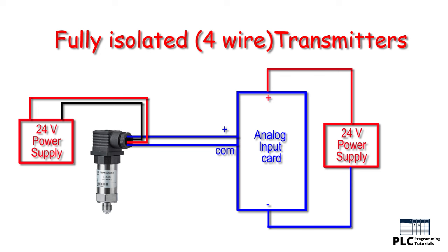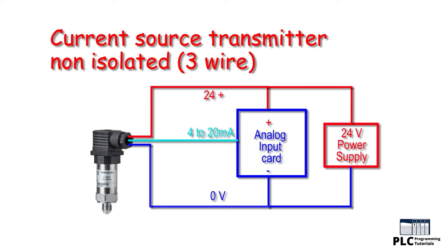3-wire non-isolated transmitter: this is the most common configuration of modern 4 to 20 milliamp transmitters. The transmitter and control panel can use the same 24V and 0V DC lines. The 4 to 20 milliamp signal flows through the 24V DC line and the signal line to the PLC controller. This type of wiring configuration needs only a 3-core cable from the control panel to the transmitter, and a common power supply is used for both the transmitter and the control panel or PLC.